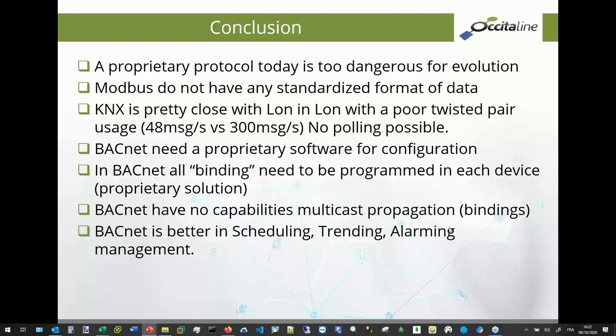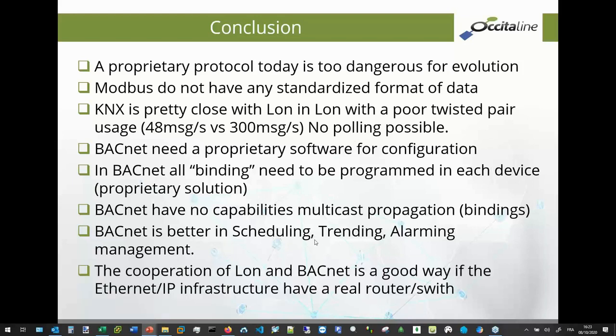BACnet has no capability to send a multicast propagation. If you want to send a switch on or occupancy to just one floor, you need to send occupancy, occupancy, occupancy, occupancy for every room, and you send a lot of messages. Or you send a broadcast, and in the case of a broadcast, every device receives this information.